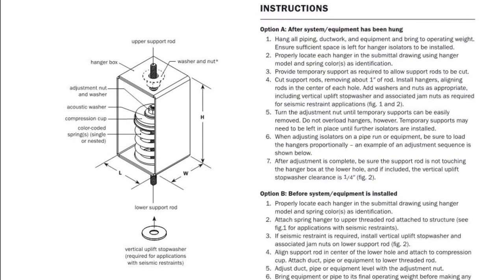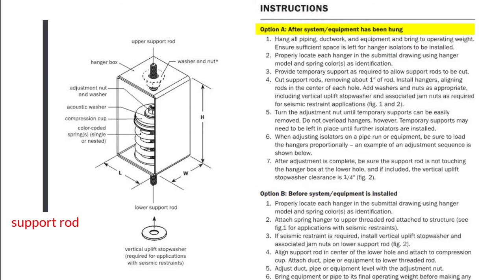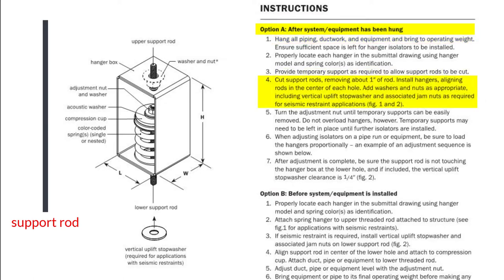The instructions are split into two options. Option A describes how to install the isolator after the system or equipment has been installed, and option B describes how to install along with the equipment or system. With option A, the equipment or system is hung, filled, and brought up to operating weight, temporary supports are placed on the support point, and then the support rod is cut, removing about an inch of rod.